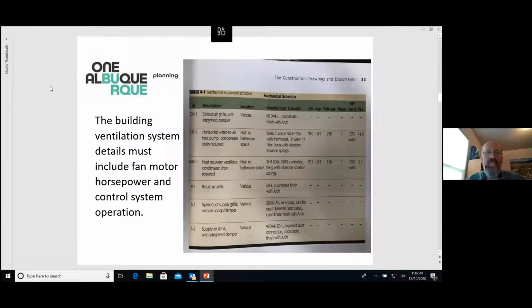So the vent system details are going to look a little different, or maybe not. You need to include fan horsepower and control system operation. So there's a snapshot I took. I'm sorry it's not super clear, but on the right side you can see the horsepower is in watts, phase, voltage, cubic feet per minute. You're getting more information that specifies that it does in fact fall into the proper requirements of the IECC.